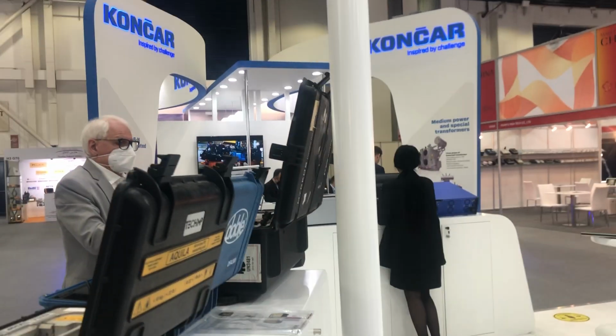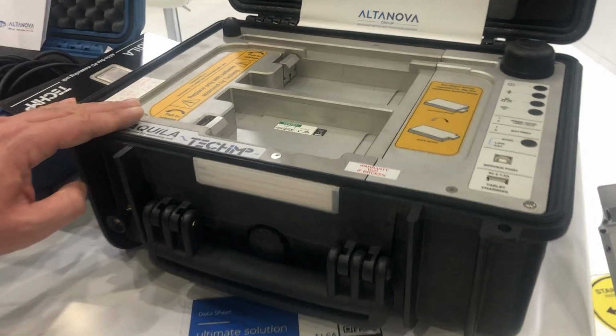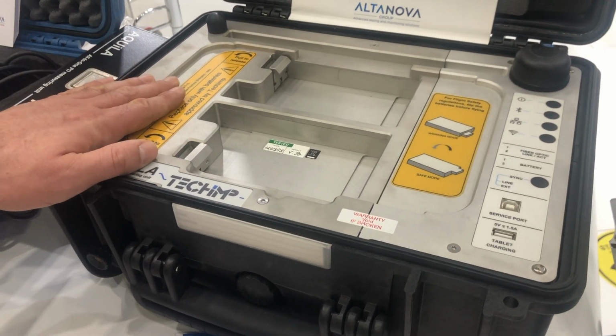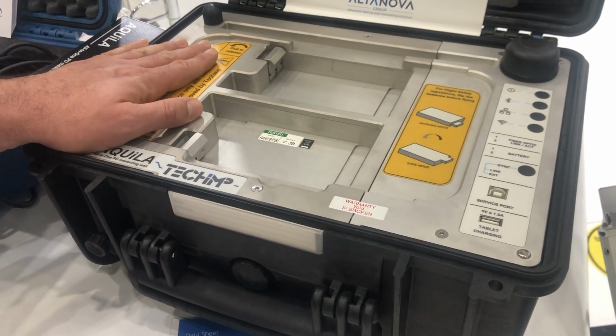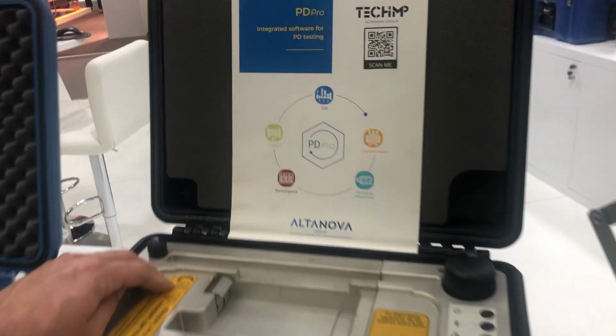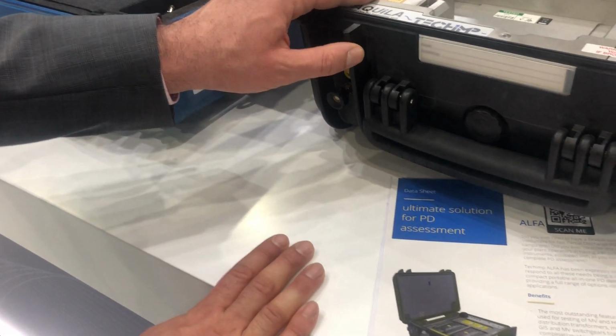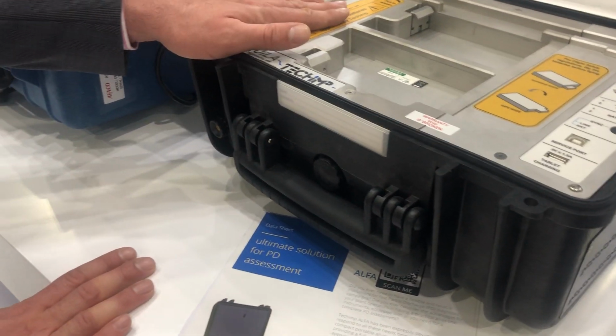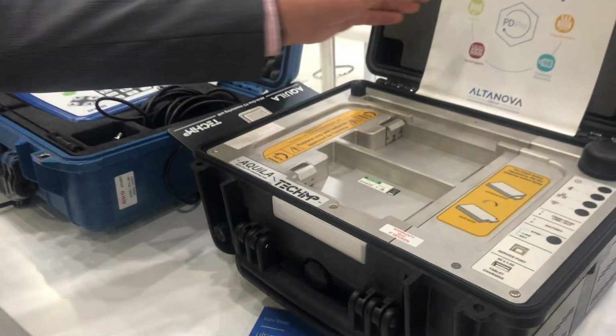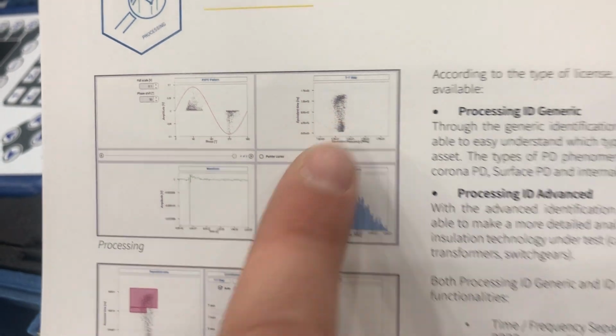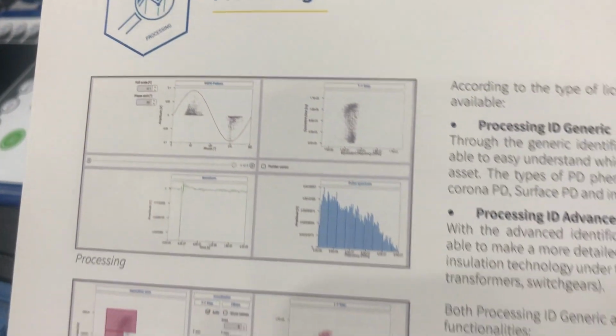So here, then, we have some more devices. The first one of those is an Aquila from Techimp. It is a universal device for testing of partial discharge. Whether you want to do an online test or an offline test on a GIS, medium or high voltage cable, transformer, medium or high voltage, or you want to test, for example, a cubicle, you can do it with this device. It has 3 channels, and with the multiplexer you can get up to 6 channels. The biggest advantage would be the TF map, which allows you to pass from the time domain to frequency domain, and thus cancel the noise and separate the sources. A patented function of the Techimp company.